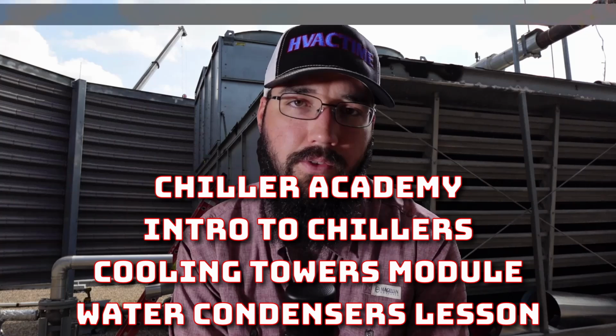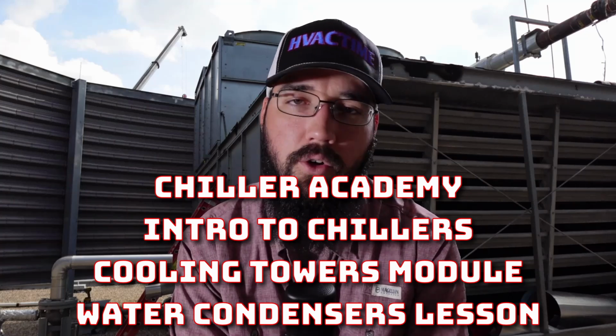Cooling towers are an essential part of every chiller system. When I say every chiller system, there are systems out there, and we're specifically honing in on water-cooled systems that use things like geothermal, or lake water, ocean water, ships. Ships have chillers in them, using ocean water to run their condensers. There's a lot of power plants set up by a lake intentionally, because they use that lake water to cool their cooling systems and chillers, and a lot of them use natural draft cooling towers to accomplish that.